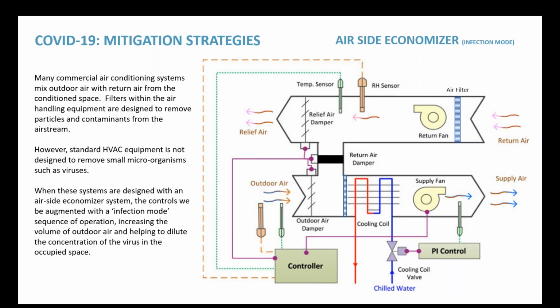Well, one way is to take a recirculating unit and make it a 100% outside air unit by closing that return air damper and not allowing any air recirculation. Now, this may be appropriate for some equipment, but not all equipment, or potentially it's appropriate for certain outdoor air conditions, but not others. So this is where the previously mentioned system analysis becomes key, because you need to look at, in the case of an existing system or even a new system that's in design, what is it actually capable of? Not necessarily how do we want to normally operate it.